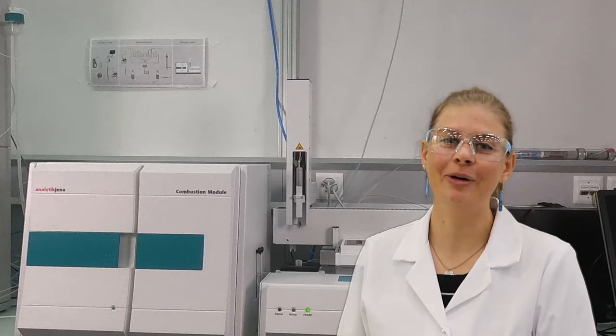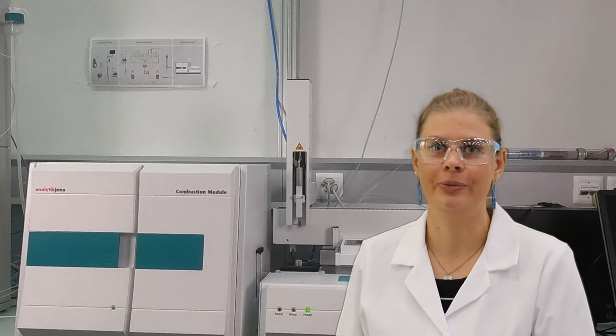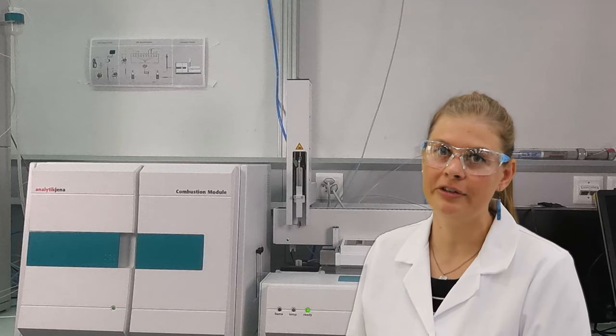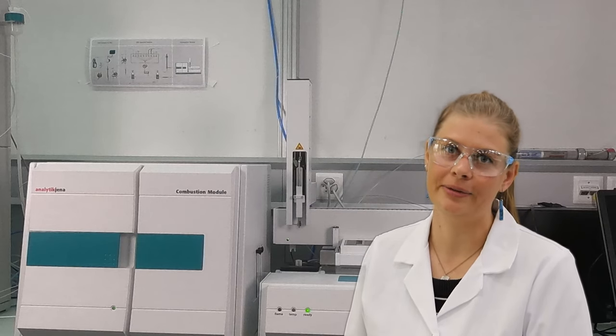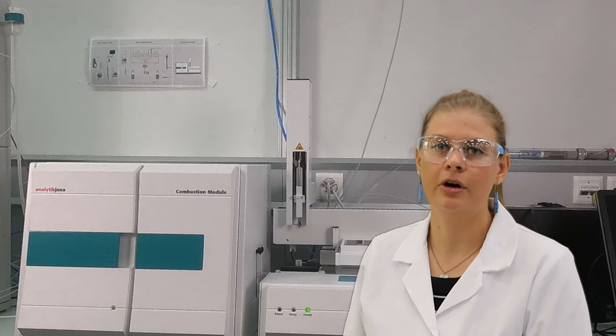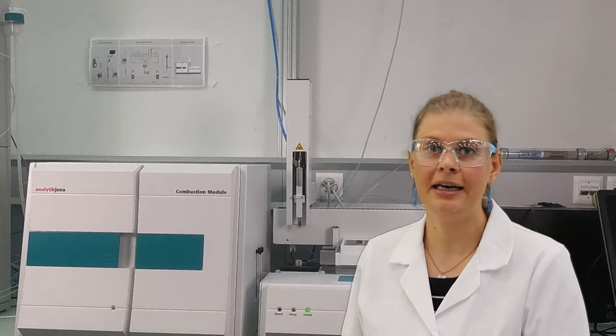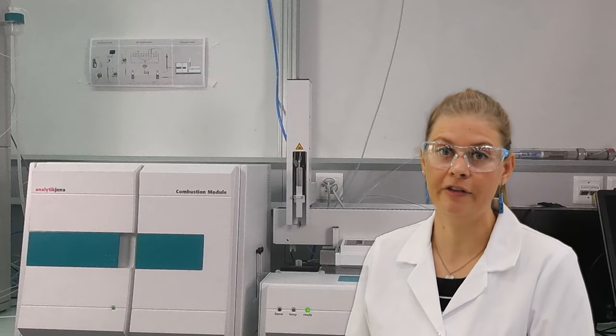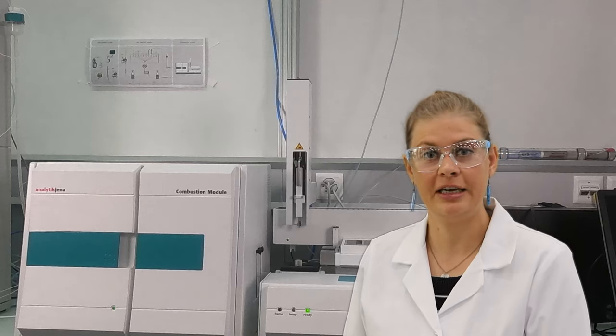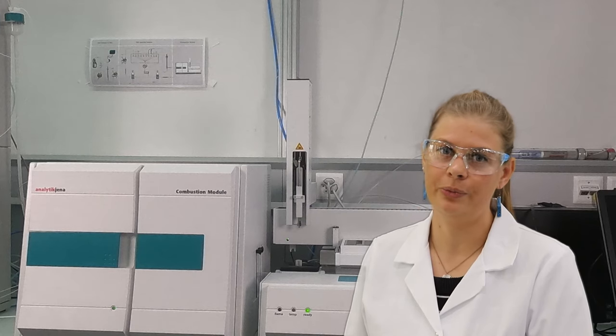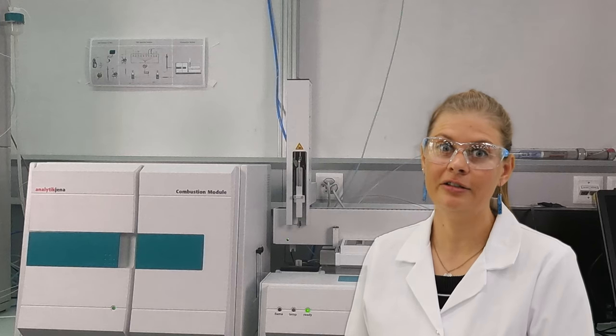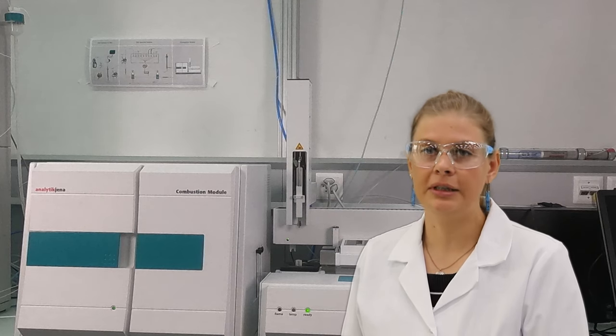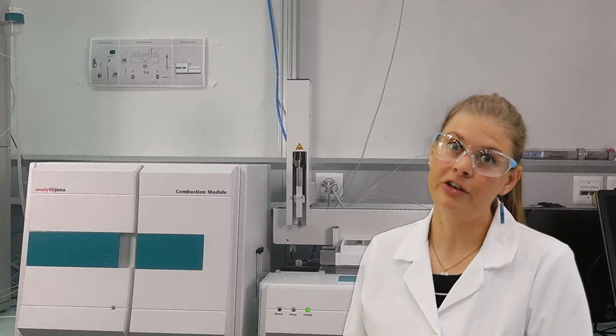You are probably wondering how often you should exchange the combustion tube. There is no definite answer to this question, as it depends on your samples and on the number of analyses you run. The performance of your combustion system is verified by analyzing certified reference materials. As long as the recovery is within the set specifications, there is no need to exchange your combustion tube. When the recoveries of all analytes in the CRM are out of range, you will need to investigate and possibly exchange the tube.